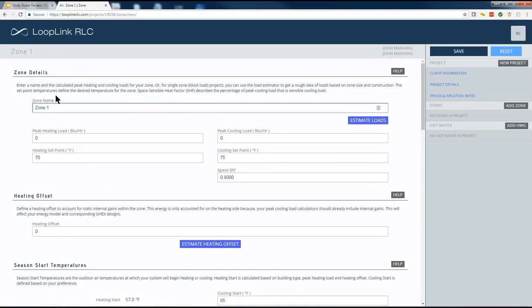As soon as I do, you'll be taken to the zone page where you can go ahead and name your zone. I'm just going to call it block load for the entire house here. For the sake of example, let's pop in heating and cooling load. These are going to come from the results of your ACCA Manual J load calculations that you performed.